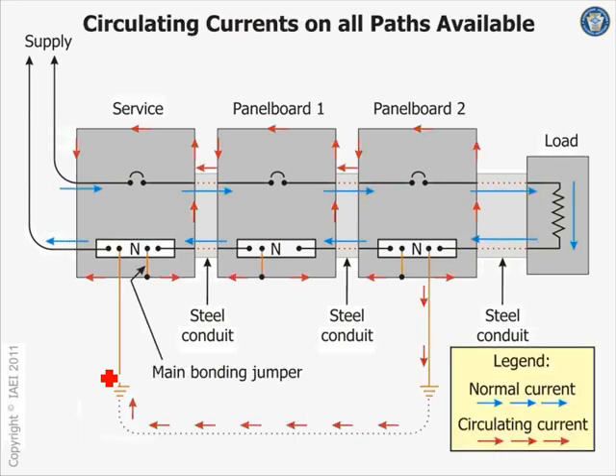Go to your next slide, that one there. Let's say you've got an equipment rack plugged into panel 2, a metal rack sitting on concrete. Inside that equipment rack you have gear that has a neutral tied to ground inside the equipment. So you effectively have that problem: a steel rack sitting on concrete, and inside the rack you've got equipment where the neutral is tied to ground inside the gear.